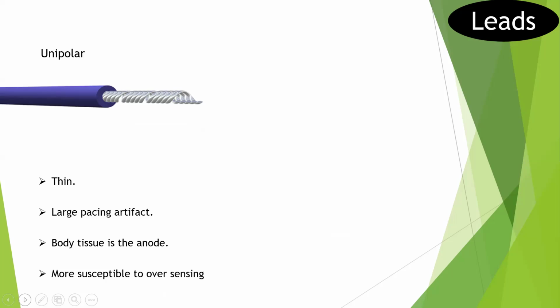The characteristic of this lead is that it is normally very thin and has a large pacing artifact, because the area between where the stimulation is delivered and where it gets back to the device is very large, from the tip of the lead up to the can of the pacemaker, depending on where the pacemaker is located. If subpectoral, that's going to be a very large distance. If it is an abdominal device, like with epicardial leads, then the artifact is going to be less.